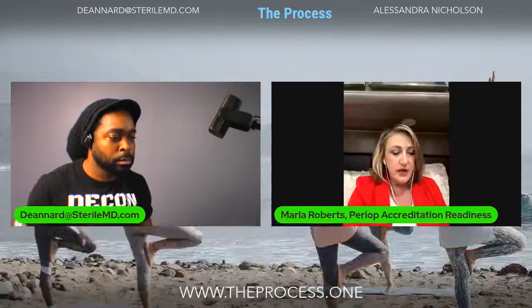It really does help lead you, because I've gone into facilities that have been closed for 6 months and they want to reopen them. And the people walked out with everything sterile in there. And the people that wanted to reopen it thought, it's fine, we can just reopen it. And it's not, because temperature, humidity, pressure, none of that had been monitored during that 6 months of being closed. So millions of dollars got thrown in the trash because of that. So that's the first thing.